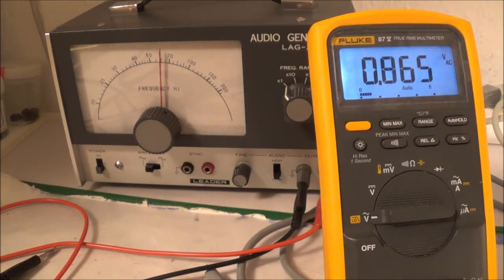And I'm getting ballpark 0.865. Now I can divide the 10 by this 0.865, and I think I said the turns ratio should be around 12.2 or something like that. So take the 10 and divide that by 0.864, equals a turns ratio of 11.57, which is getting a lot better now. It's pretty close, that's what we're looking for.